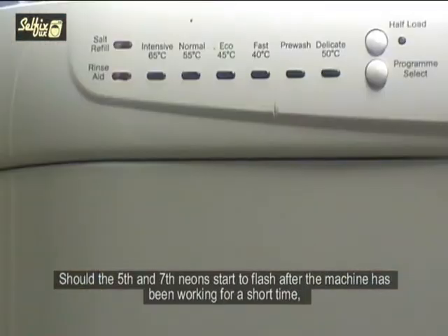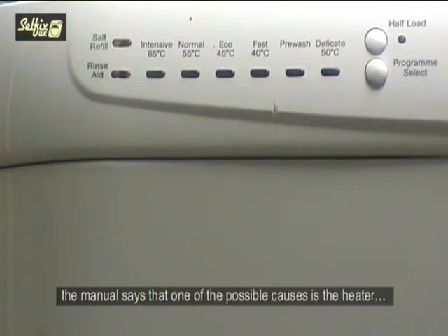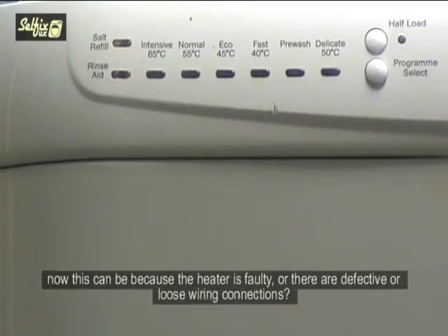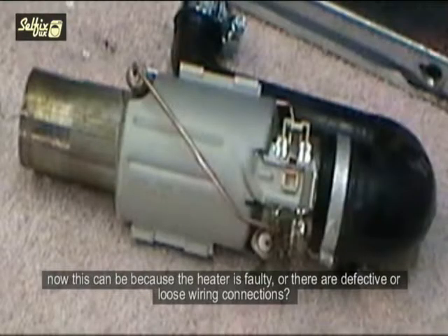Should the 5th and 7th neons start to flash after the machine's been working for a short time, the manual says that one of the possible causes is the heater. Now this can be because the heater is faulty or there is a defective or loose wiring connection.